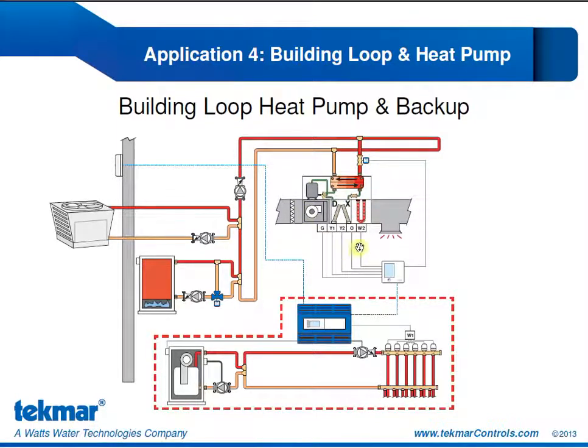We have a building loop being maintained within a certain temperature range by the boiler and the cooling tower. And there are individual heat pump units. So our first stage of heat is the radiant, second and third stage of heat provided by the heat pump with the Y1 and the Y2 connections, a fourth stage of heat with the electric strip backup, and when we switch over to cooling, we have two stages of cooling with the Y1 and the Y2 heat pump connections.